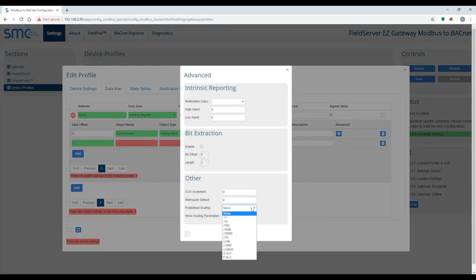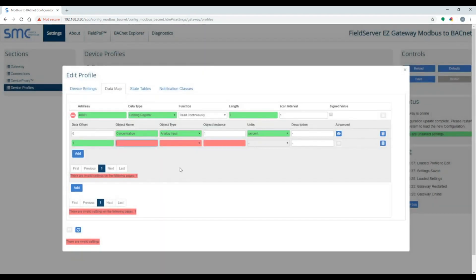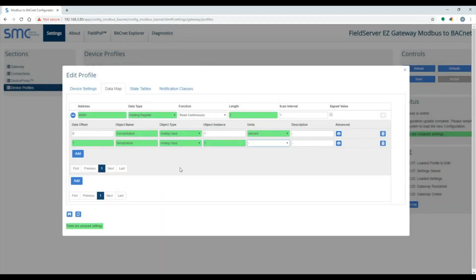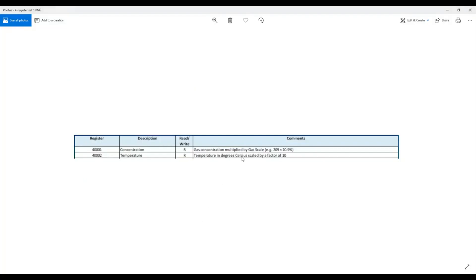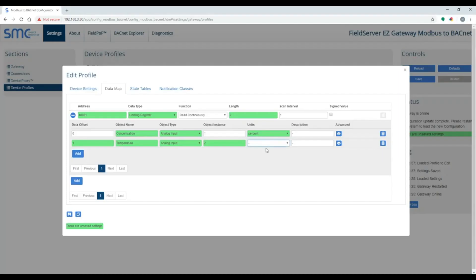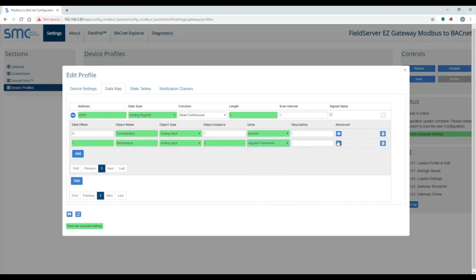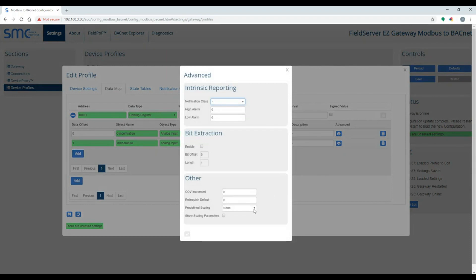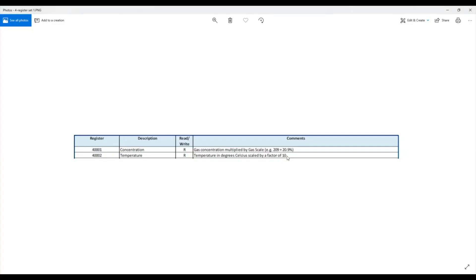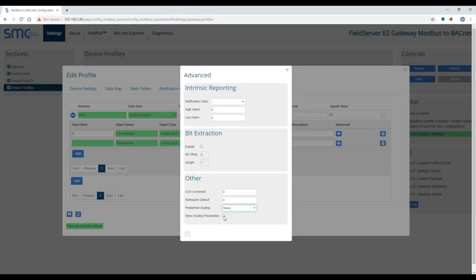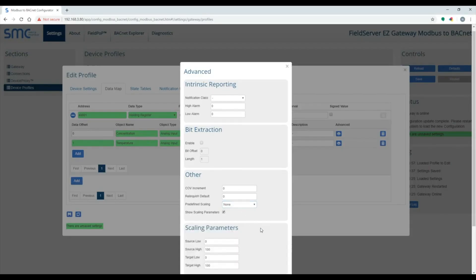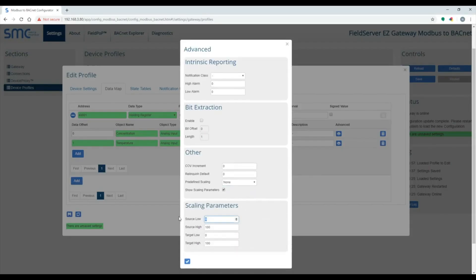The scaling is done in the advanced section. The temperature point has units in Celsius, and also needs to be divided by 10. I will be converting this to Fahrenheit. There is no predefined scaling for dividing Celsius by 10, then converting to Fahrenheit, so you will need to click on the Show Scaling Parameters button to specify your own scaling.